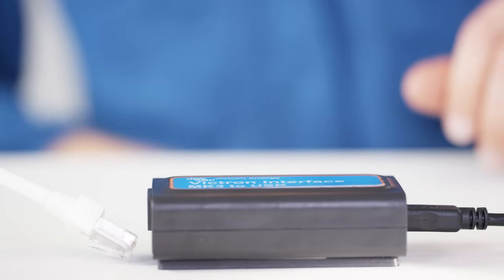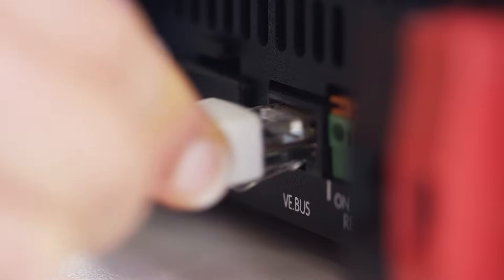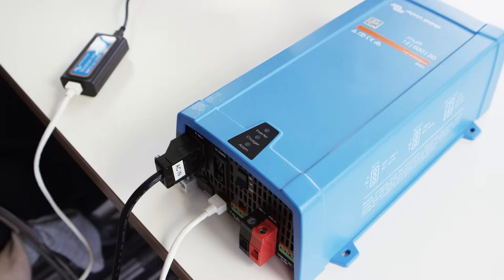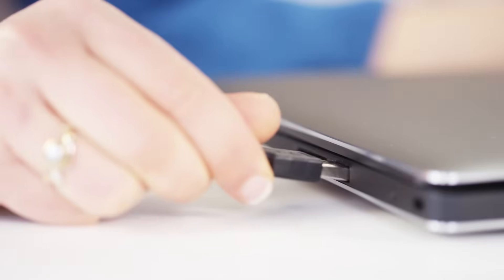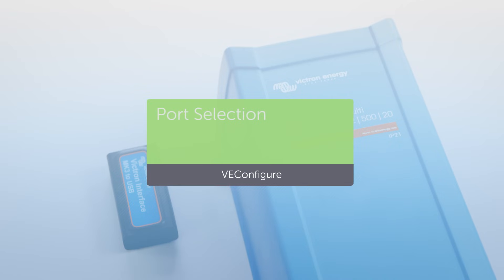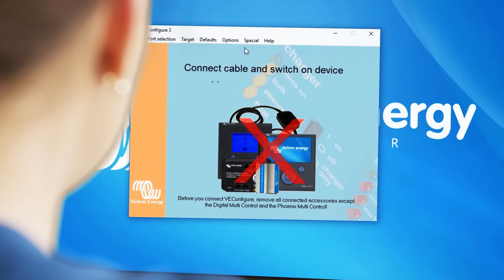First, we will connect our device to the computer. You will need an RJ45 UTP cable and an MK3 or MK2 USB. Make sure the Victron device is on. Insert the USB in your computer. In VE Configure, go to Port Selection, COM Port and select Auto Detect. You will now see Target found.